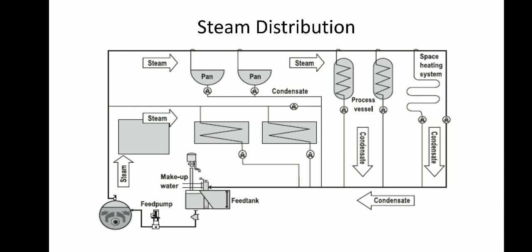Then some common factors are there in the steam distribution system. First one is the working pressure. The distribution pressure of steam is influenced by a number of factors but is limited by: one, the maximum safe working pressure of the boiler, and two, the minimum pressure required at the plant. As the steam passes through the distribution pipe work, it will inevitably lose pressure due to, first, frictional resistance within the pipe work, and second, condensation within the pipe work as heat is transferred to the environment.